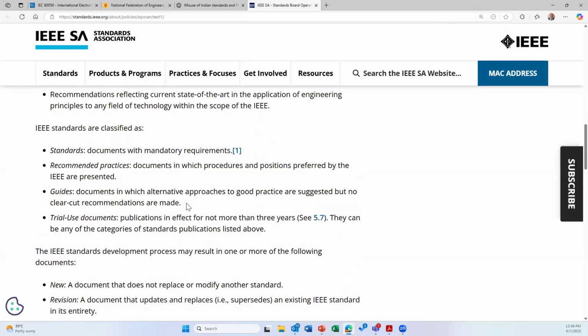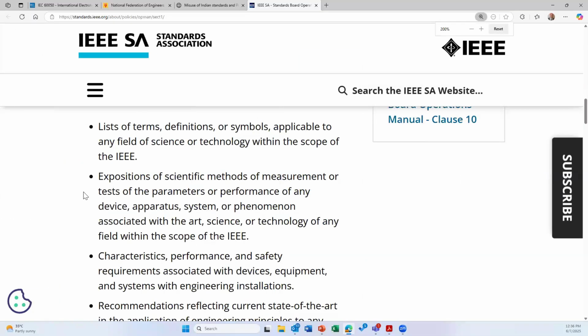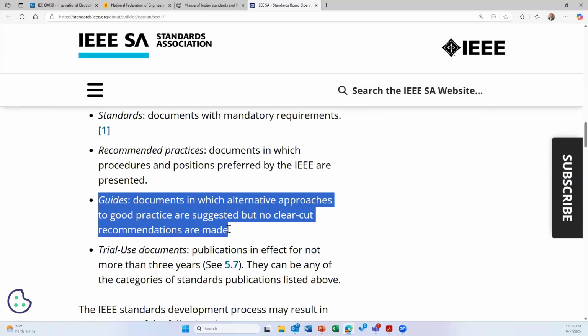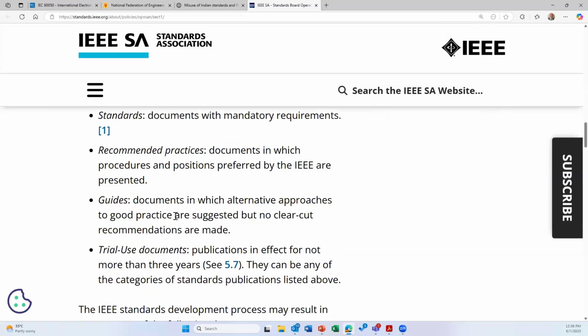Please read it carefully. IEEE 80 is a guide for substation grounding. The definition of guide on the IEEE website: documents in which alternative approaches to good practice are suggested, but no clear-cut recommendations are made. That means there is a good practice and correct method already available, and a guide is giving an alternate approach. If you want, you can use this alternate method. In the other sense, IEC 61936 gives you a very clear-cut picture of what you should do for substation earthing. So when using IEEE 80, be careful. Of course, a lot of very highly useful information is there in IEEE 80, and we also make use of it quite often, but please read the correct meaning and use it.